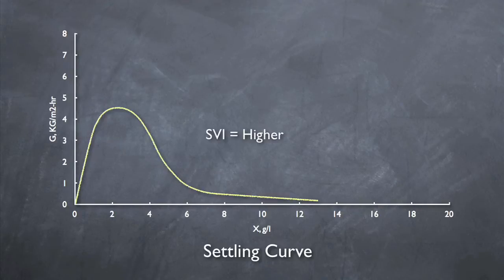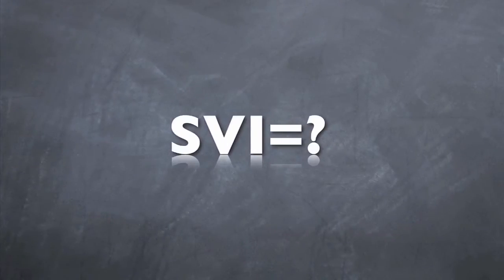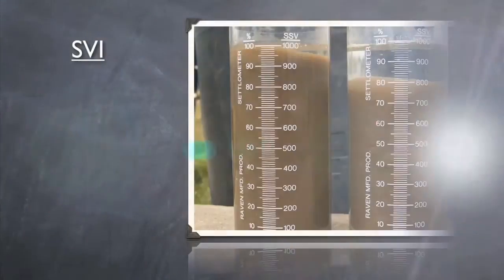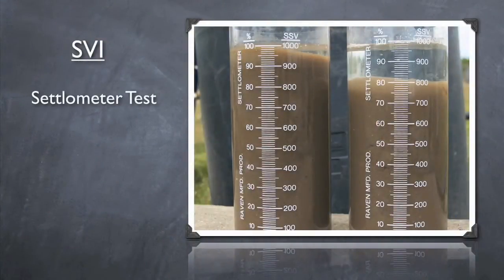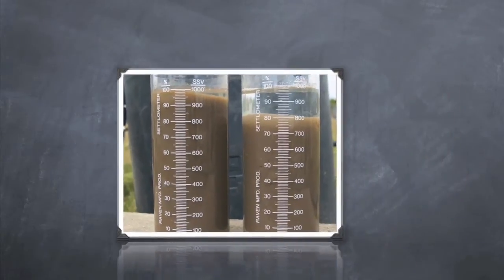So what does it matter if the curve is larger or smaller? Well, we'll find that out in a minute. But now that we know that SVI is important in determining the settling curve, how do we determine the SVI, and what causes it to change? Well, the SVI can be determined by performing a settlometer test. Also, if you can, use a diluted sample to determine your SVI. This will allow for more accurate results, especially when the SVI is higher.